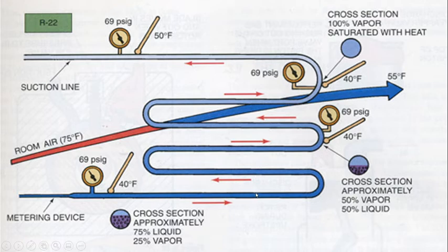As it's going through here like the pot, the air is just starting to heat this refrigerant. Well, when it gets to that temperature where it's 40 degrees and it starts bubbling inside this copper tube, just bubbling away just like that pot was boiling, it's going to accept more and more heat. So when it hits latent heat and it starts boiling, it will accept more and more heat, more than it did down here. When you see the change in color here, it's going from a dark blue to a lighter blue.